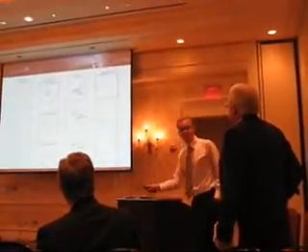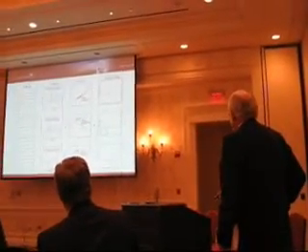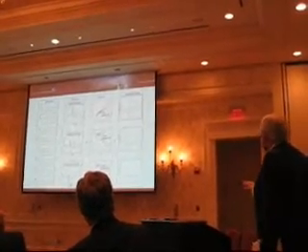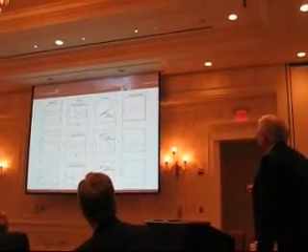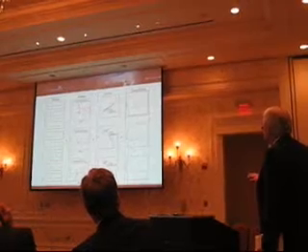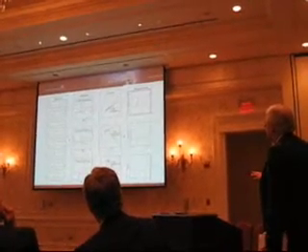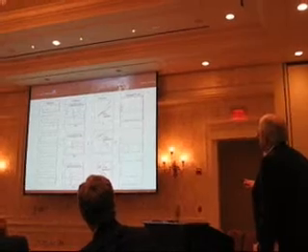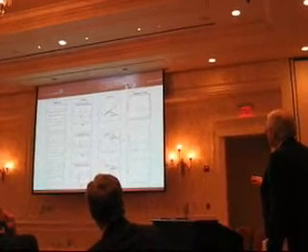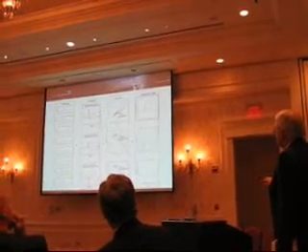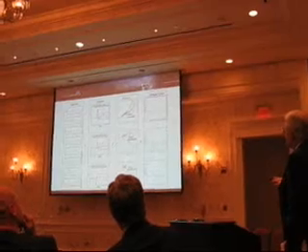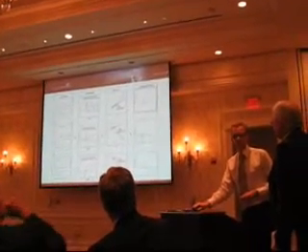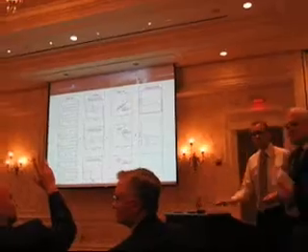We make an XYZ transformation, look at only the ST segments, and use these to form a PCA-based lead. So we optimize for information from the ST segment. And this is the lead that we use. This gives us quite good stability in our measurements.